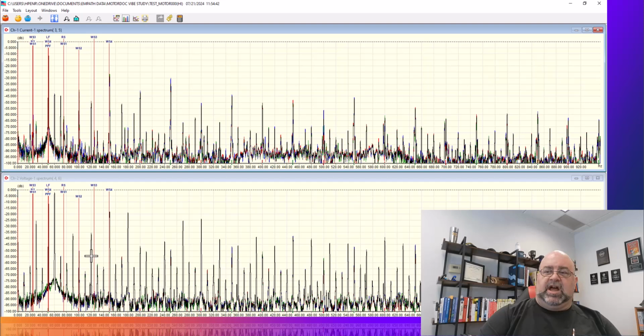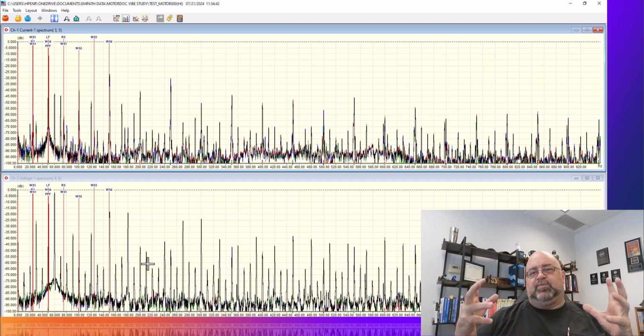Some of those peaks are not showing up in voltage. So that means that that is most definitely a winding stress. And I'll see that on VFDs in particular. So the old winding short type signature that everybody kept throwing out, because the original study was somebody twisting wires together and that must be the cause, is just the short. It didn't consider that it involved any type of sparking, arcing, or partial discharge going on in windings. So when we have advanced partial discharge in windings, we see it as this signature in electrical signature analysis. So with that, that's data collection. That's that real quick, and then of course we have casting voids, but let's do one last thing.